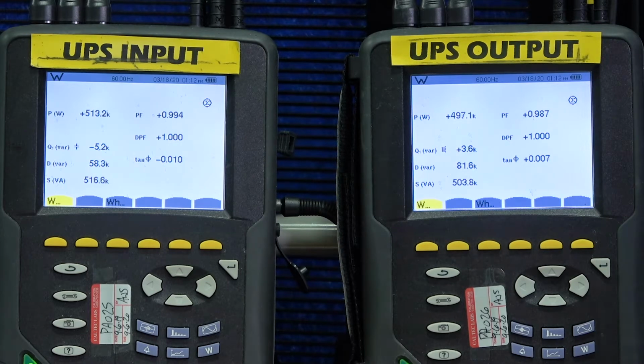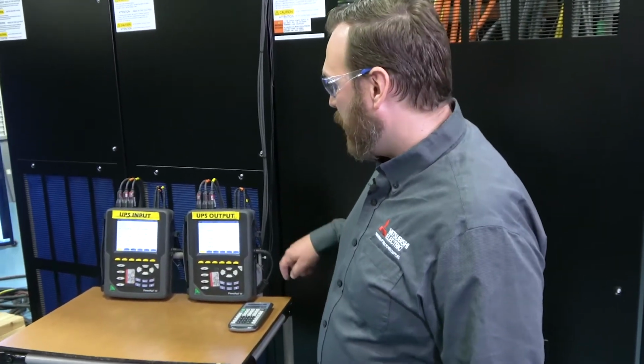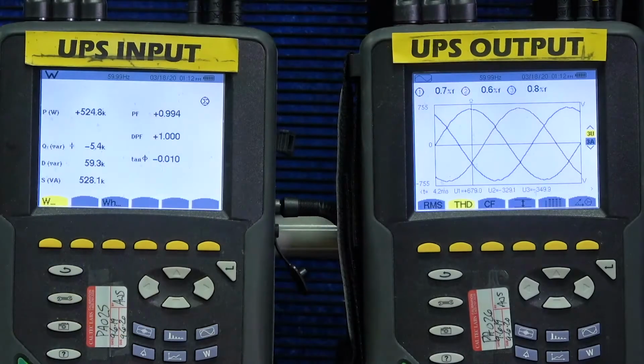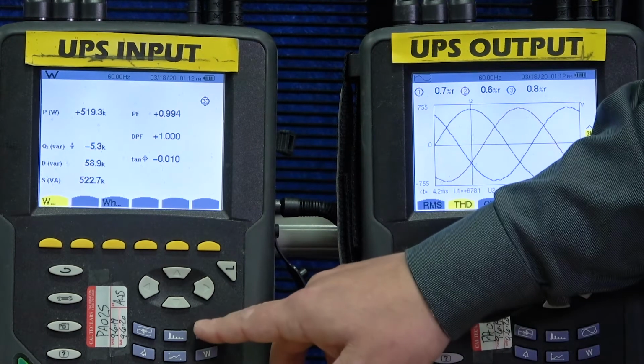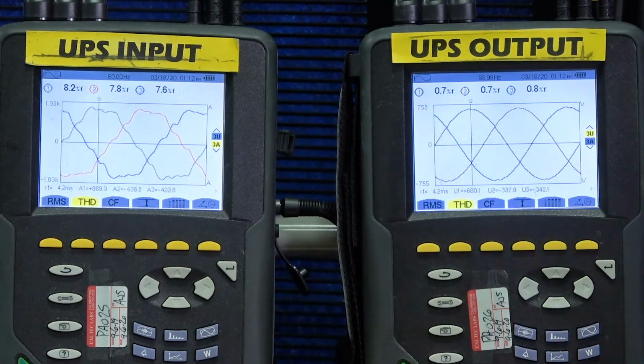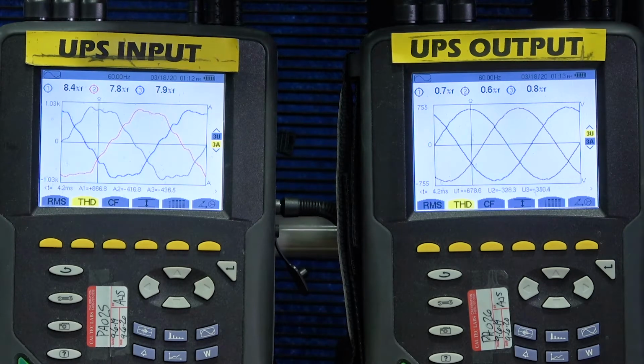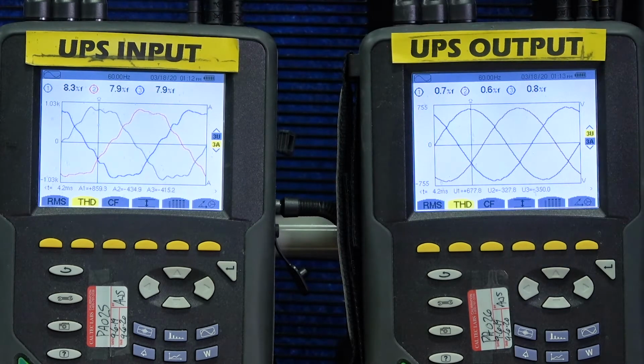So we've increased the output load to 500 kilowatts, or 25% of a 2 megawatt UPS system. We can see the output harmonic content really has not changed very much on the output voltage. But another interesting thing we can see is the input harmonic content of our converter. With 25% load on the UPS, we now have about 8% input harmonic current on each of the 3 phases of our UPS input.